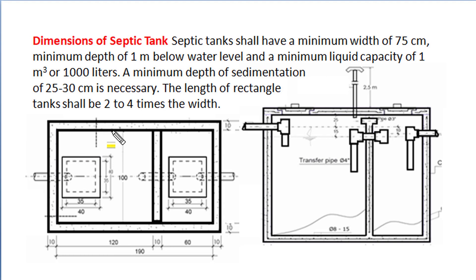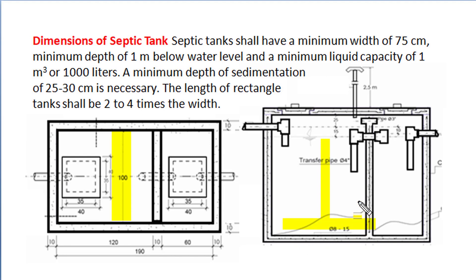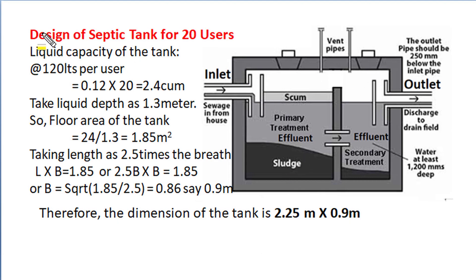The plan and elevation of a typical septic tank is shown here, and we can understand the dimensions of the septic tank from these drawings. The septic tank should have a minimum width of 75 cm — in this example the width is 100 cm. The minimum depth below top water level should be 1 metre — here it is 1.8 metres. The minimum liquid capacity of any septic tank should be 1 cubic metre or 1000 litres, and a minimum depth of sedimentation of 20 to 30 cm is necessary. The length of the septic tank should be 2 to 4 times the width, and depth should be from 1 metre to 2 metres below top water level.